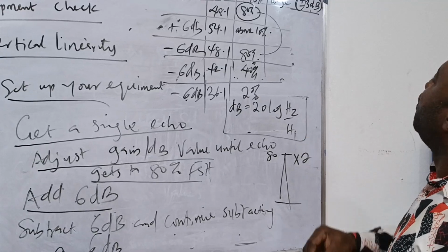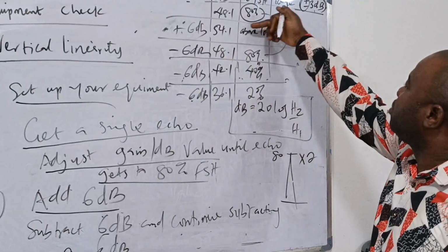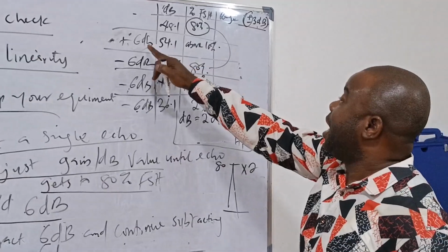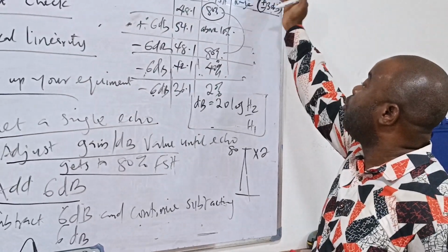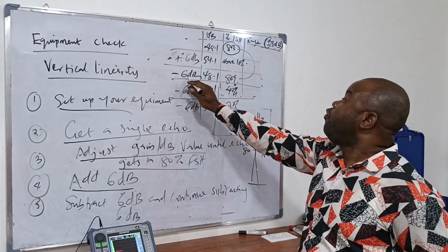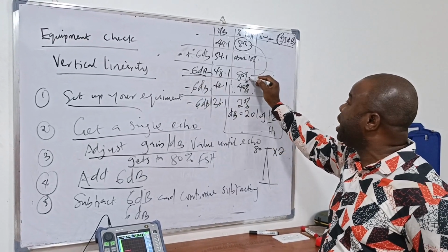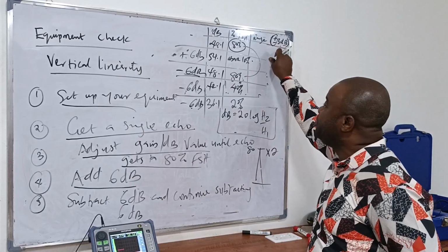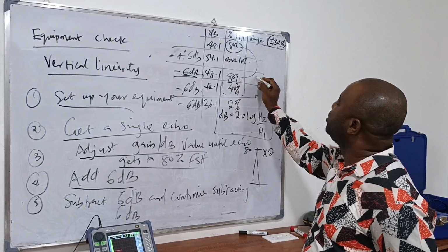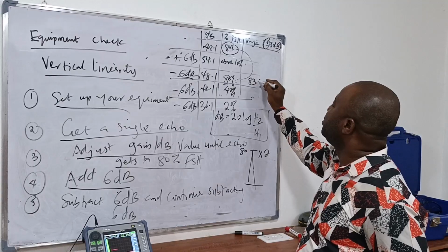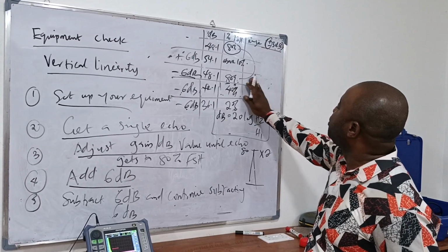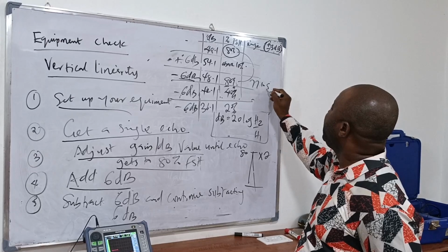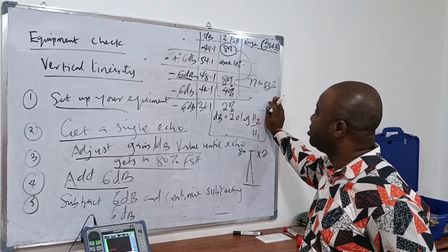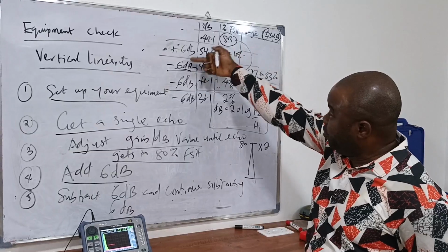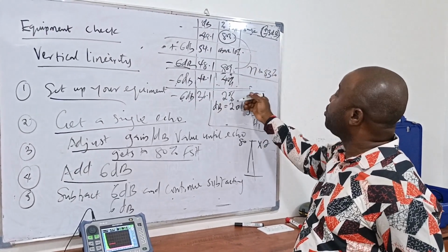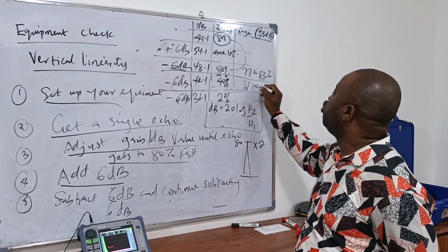So what does this mean? If I add 6 dB, of course, it's going to go above 100%. We are not going to see it. If we reduce 6 dB, we should come back to 80. What this plus or minus 3 dB means is that I should be getting between 80 plus 3, 83, and 80 minus 3, 77. So I should be getting 77 to 83% of my full screen height. If I remove 6 dB and I'm at 40, plus or minus 3 dB, it will be 37 to 43%.